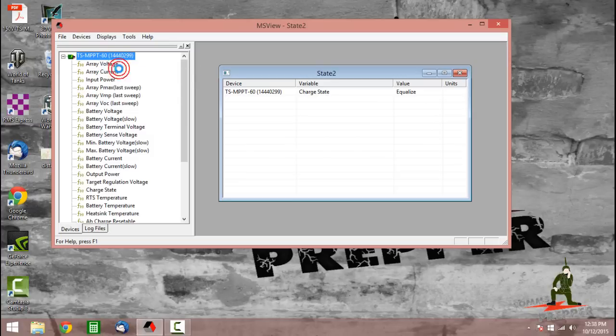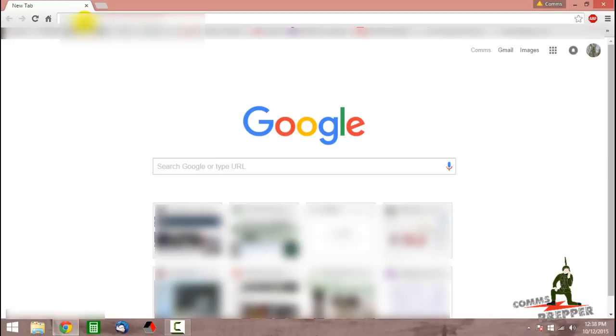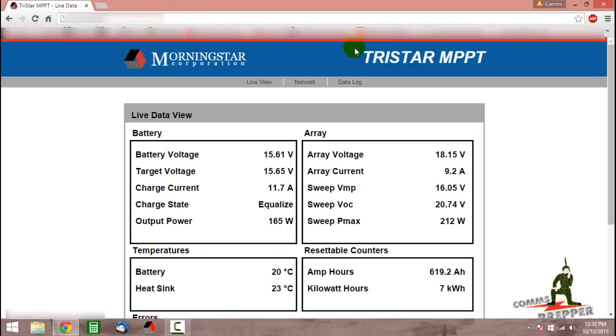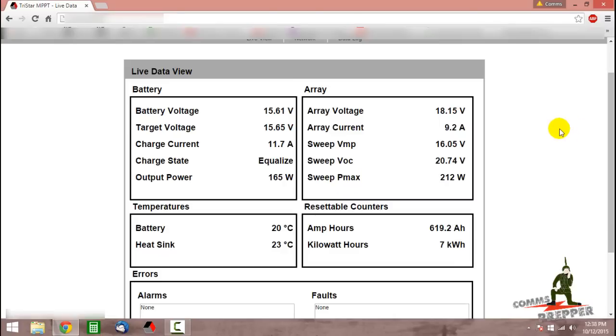We'll go ahead and hit Disconnect. The icon is now red. We'll close out of MSView and open the web browser one more time to make sure equalization is showing in the web interface for the charge controller. The charge controller is now in equalization — it's boosted the battery voltage from 13.2, the float voltage, up to 15.62. That's the equalization voltage, plus a little additional based on the temperature of the battery. We're putting 10 amps of current into the battery and we are in equalization mode, so we're now equalizing those batteries.